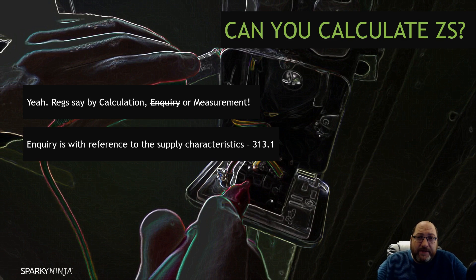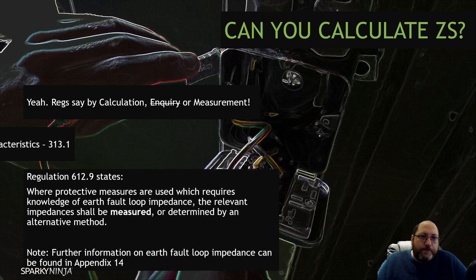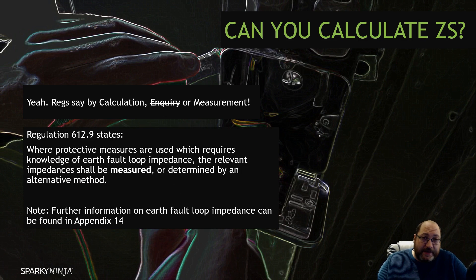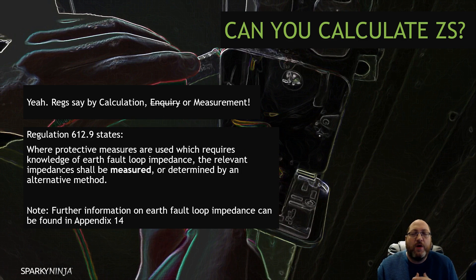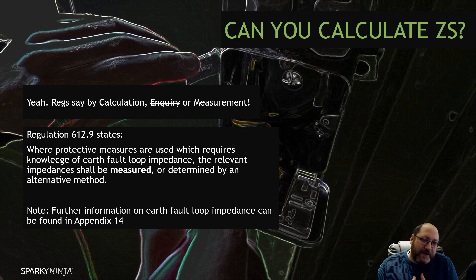You can only inquire a ZE or PFC — you do that when you're doing a new design and the supply characteristics are being collected for that part. Now, regulation 612.9 states that if your protective measure requires knowledge of the earth fault loop impedance, the relevant impedances will be measured. Or they'll be determined by an alternative method.